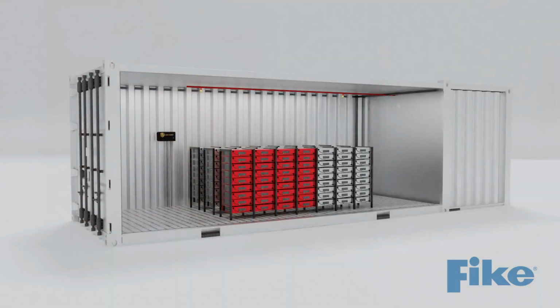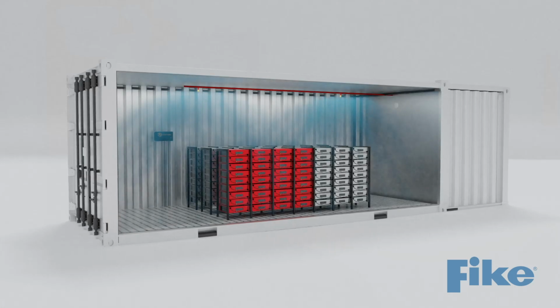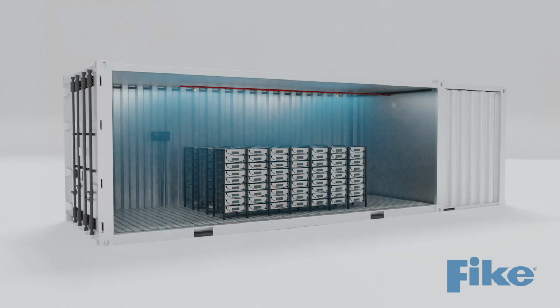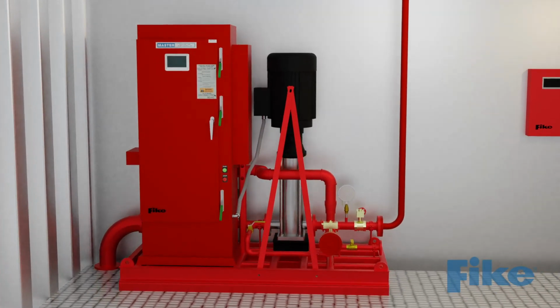When a fire is detected, Fike is going to recommend a water mist system to protect that space. So it's going to flash to steam, it's going to absorb the heat of any fire or even the heat given off in the thermal runaway process. And if you're using a pumped water mist system like Fike's DuraQuench system, you've got a continuous water supply for as long as you need it, for as long as the event occurs.